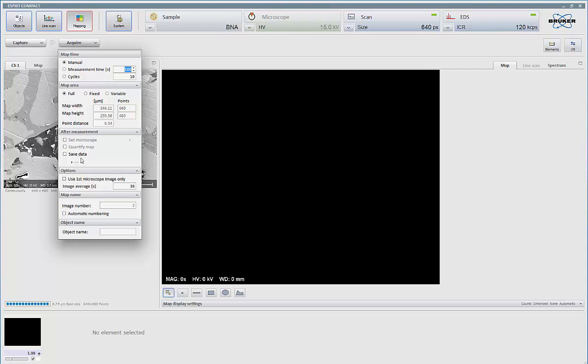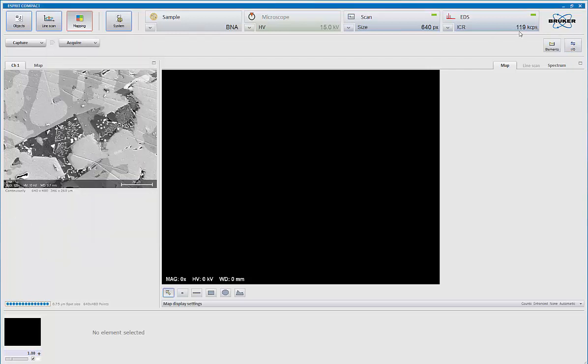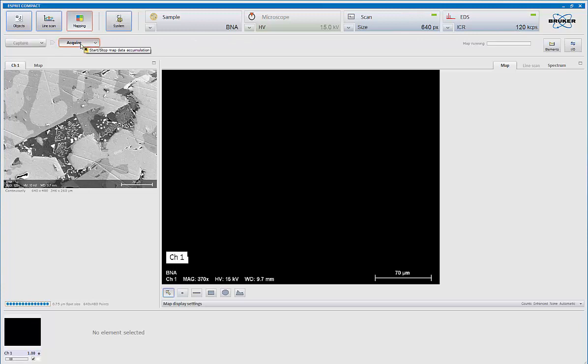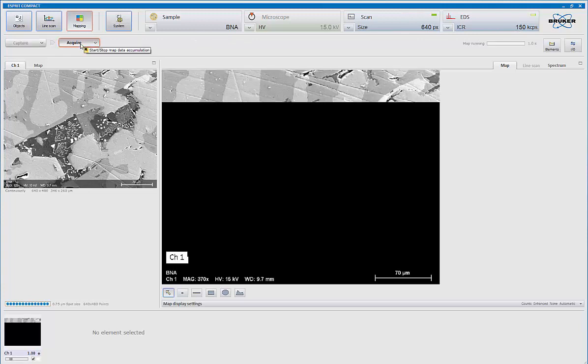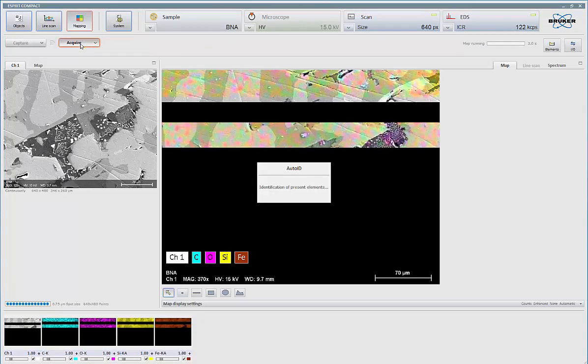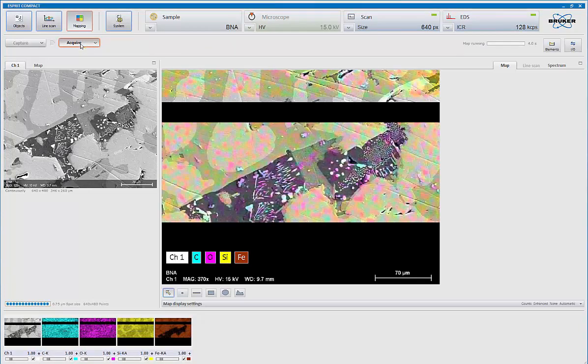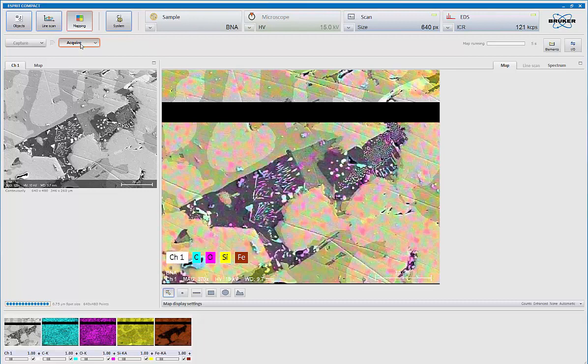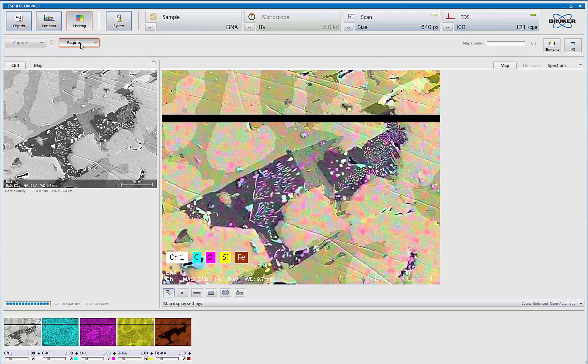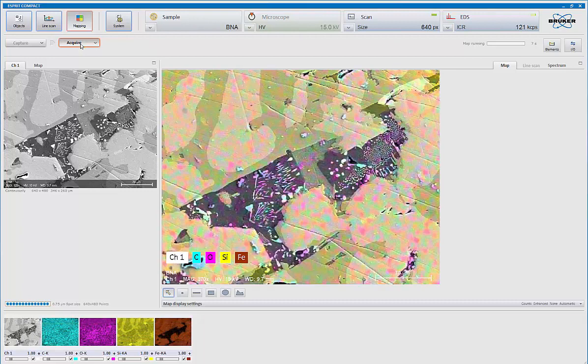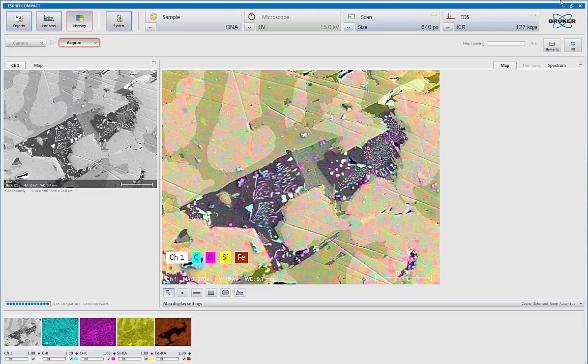After measurement, I can predetermine exactly where I want my data saved, so I can have it automatically save the information for me. I can set up the averaging for the live image that's collected with it, automatic numbering again, and this is for any objects I extract within the map itself. I'm going to stay in manual mode right now, I'm currently at 120,000 counts a second, I'm going to hit acquire. Now if I haven't told it any elements, the system will automatically do an automatic ID and select the major elements that are coming in.